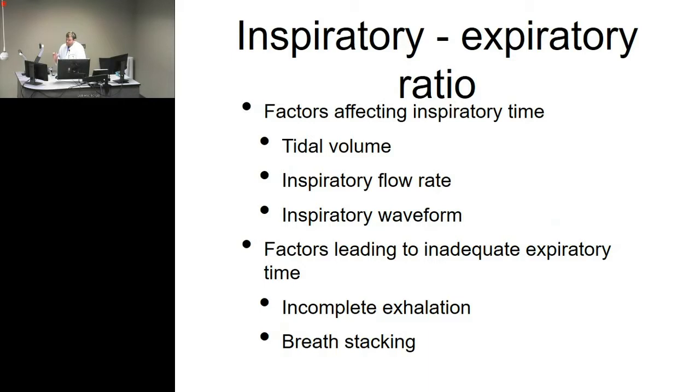Now, the flow adjusts a little bit, but what if I lower my breath rate from 20 to 8 or 10? Cut that in half. Now I've got 10 breaths, for easy math, so I'm getting a breath every 6 seconds. My flow rate's still set at 60, so I'm giving that 500 mils in half a second, but now I've got 5.5 seconds on an exhale time. And so that's where rate, volume, and flow all will kind of adjust.